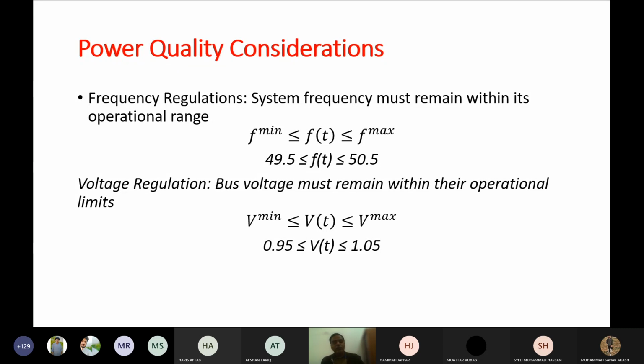In your 220 kilovolt line, your voltage should not exceed 230 kilovolt, and should not be less than 210 kilovolt in a high voltage line. This is 0.95 to 1.05 per unit, meaning it should not decrease or increase by more than 5%.